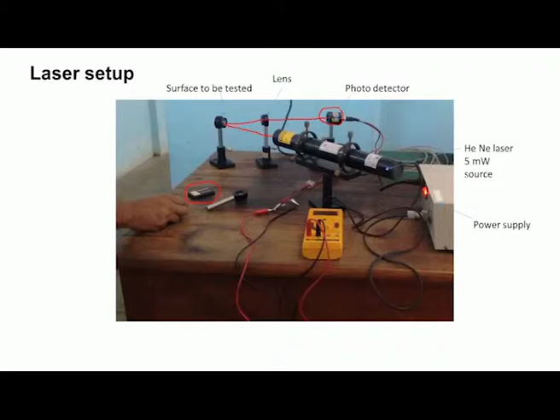Now, say for the N2 surface we have some x1 millivolts, and then for the N3 grade surface, say we have x2 millivolts, and then for the N4 grade surface, say we have x3. Now, we have to keep the surface which is to be tested here, and say the voltmeter reading is between this x1 and x2, then that indicates that the surface finish is between N2 and N3. So, like this initially we have to calibrate, and then we can use this setup.